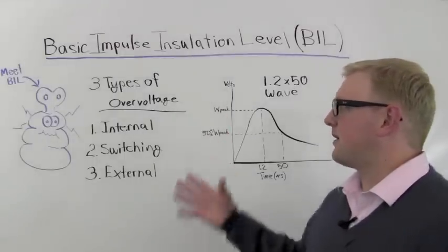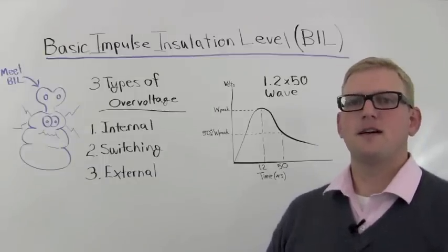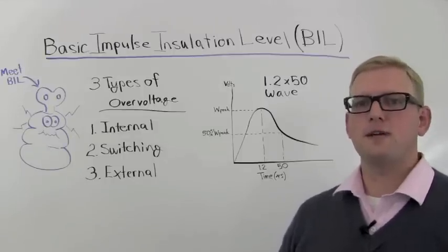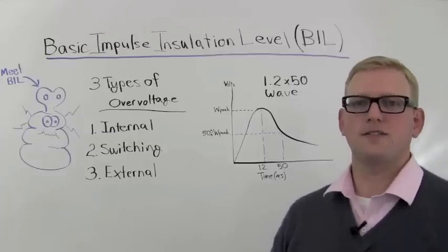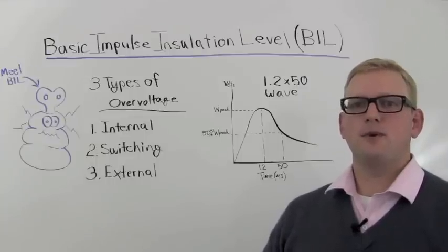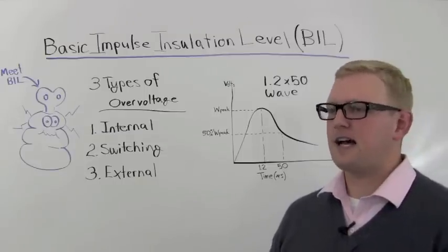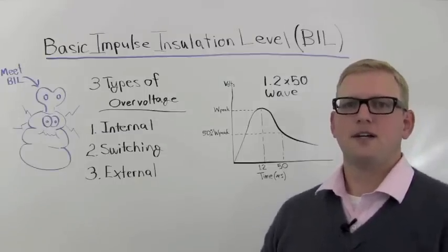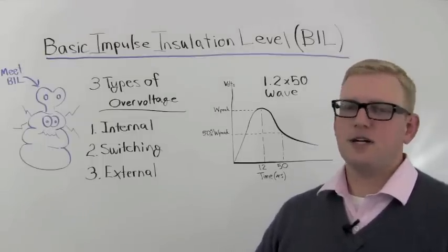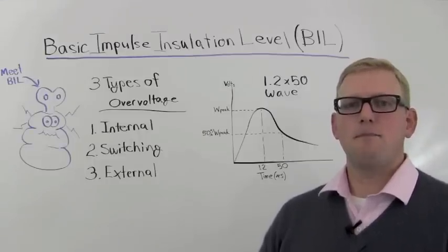How do we determine BIL? Can BIL be calculated? No — BIL comes from experience, many years of historical experience, pieces of equipment failing or being damaged by high voltage occurrences, and then research. Manufacturers want to provide equipment with the best rating, but not the highest rating. You don't necessarily have to have a high level of BIL for a piece of equipment — it can get expensive and cumbersome, and too much insulation can create too much heat. So you want to determine the right BIL level.